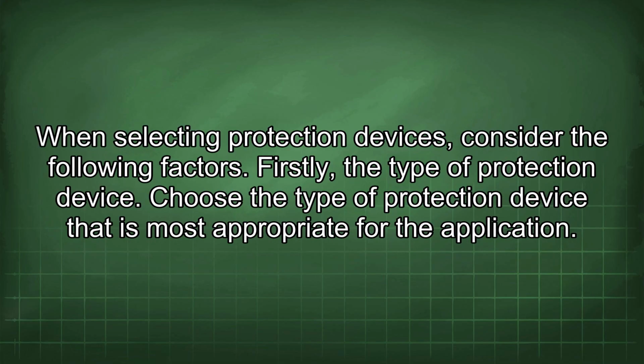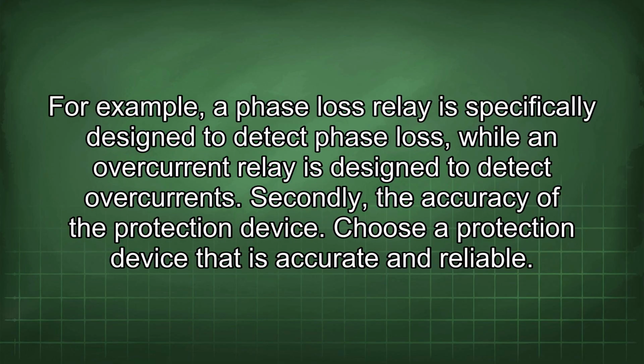When selecting protection devices, consider the following factors. Firstly, the type of protection device. Choose the type of protection device that is most appropriate for the application. For example, a phase loss relay is specifically designed to detect phase loss, while an overcurrent relay is designed to detect overcurrents.